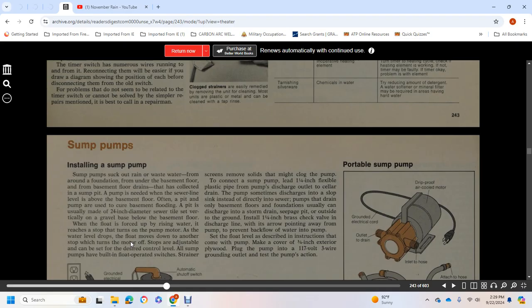Installing a sump pump. Sump pumps suck out rain wastewater that has collected from around the foundation, under the basement floor, and from the basement floor drains into the sump. A pump is needed when the sewer line is level above the basement floor. Often pit pumps are used to cure basement flooding. A pit is usually made of 24-inch-diameter sewer tile. Sewer tile is set vertically in the pit with a gravel base below the basement floor.